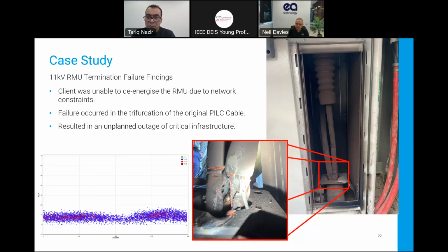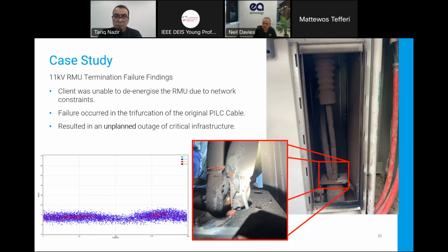The probabilities of getting a background reading much greater than about 20 dB are only about 7% or so based on stats. By the time you get to about 29 dB, which is sort of the red level for TEV reading, it's usually about 1 or 2% that you will see background readings up there. But the PRPD plots allow us to really overcome that nowadays.